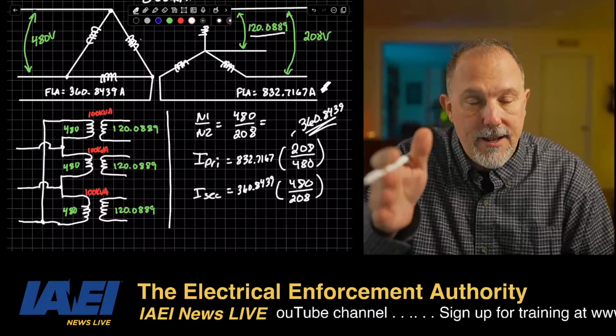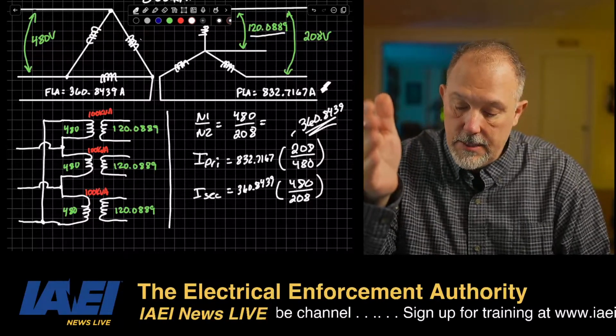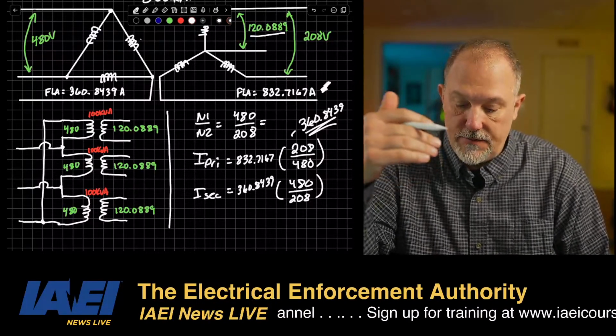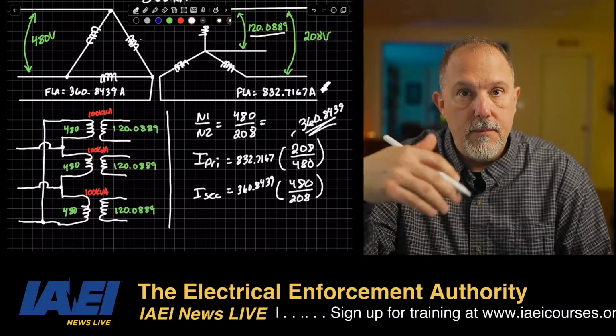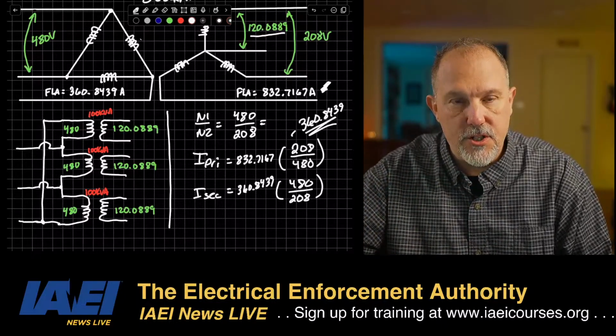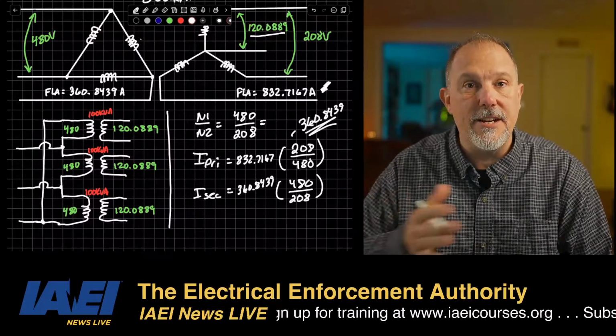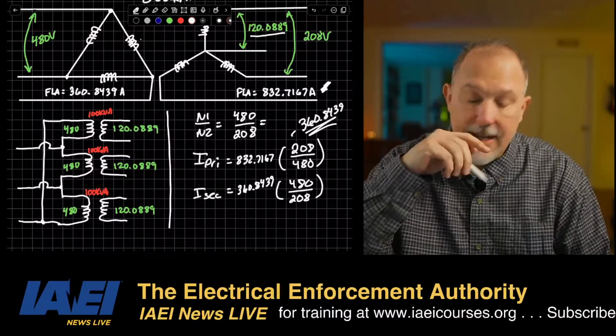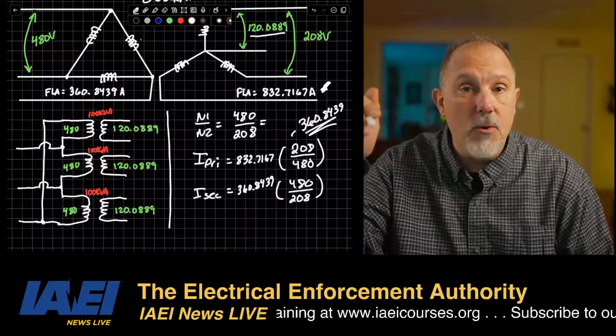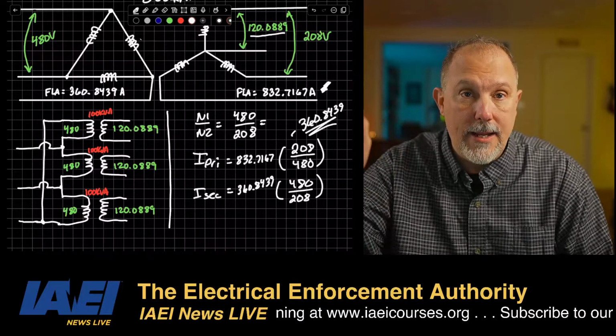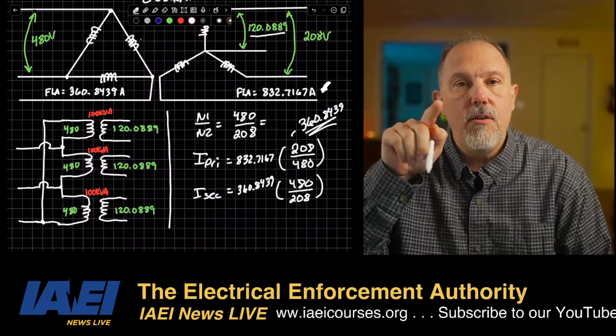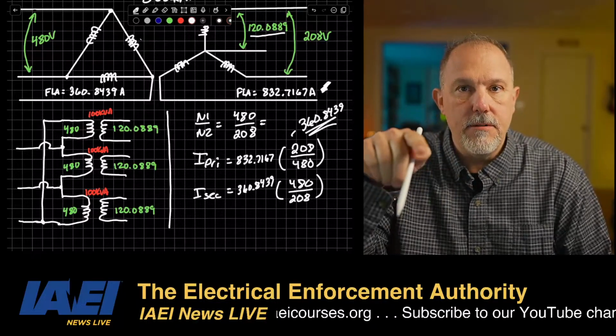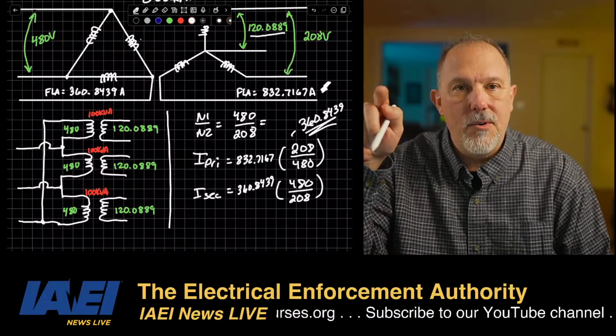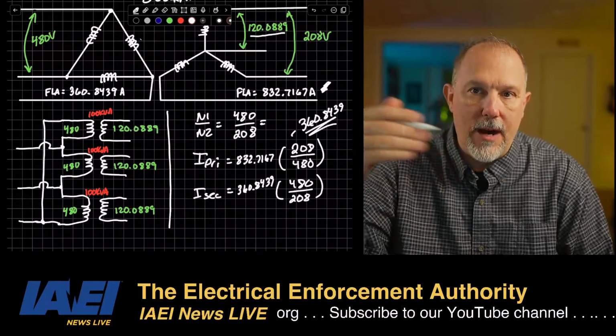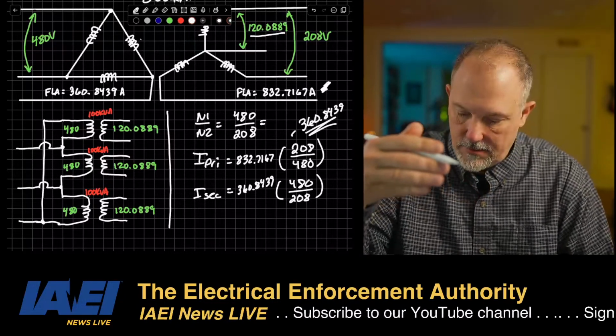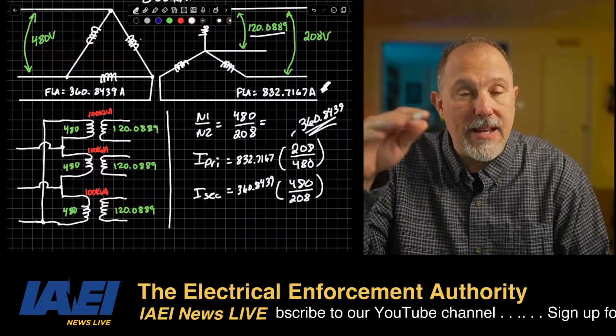What I did, and what some people disagree with, is I used the turns ratio of 480 to 208, primary voltage 480, secondary voltage 208, and I reflected my current from the secondary to the primary. I didn't use 480 to 120. Now I could, and we're going to walk through that calculation to understand where that went and why that is what it is. So we're going to do the single phase, but I just did the three phase.